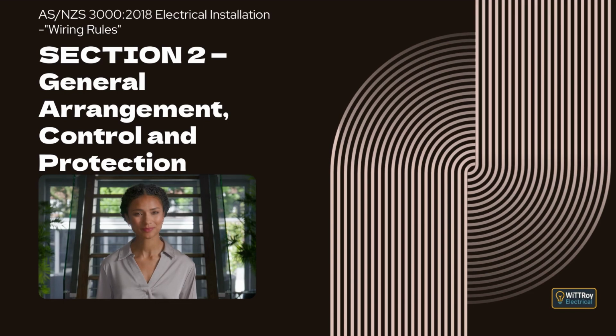Clause 2.10.7 Fire protective measures. Switchboard wiring must be installed in a way that slows the spread of fire. Openings into the enclosure must be sealed so flames or smoke cannot pass easily through. Any hole larger than 5 mm must be sealed with fire-resistant material. Larger conduits and wiring enclosures must also be sealed to prevent air movement that could spread fire.